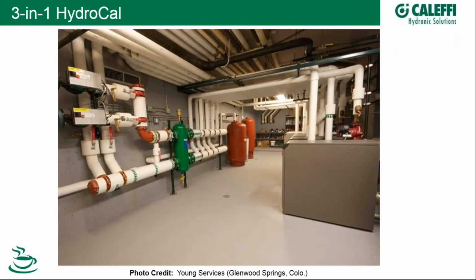So let's take a look at least one photo. Here's a job from Young Services, Mark Young, Glenwood Springs. You can see at center is the HydroCal 3-in-1 device. Here's the primary side of our system. We have 5 or 6 condensing boilers over here in parallel, feeding into the supply header, going into the hydraulic separator. So here's our primary ins, our hot water in, cool back. And on our secondary, we have a couple of pumps going out to our system and then back. These are decoupled, and these are decoupled. And notice there aren't any other dirt separators or air separators on the job.